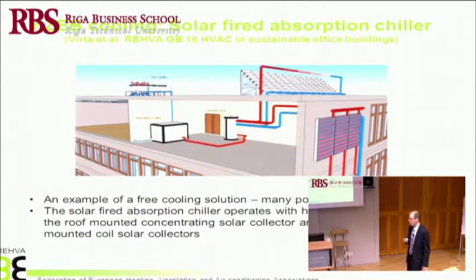In cold climate, maybe these cooling issues are not so severe. Actually, we can reduce cooling load very easily by having a relevant window size and solar shading options. And we can do this kind of buildings with common chillers. You can select, indeed, one with better seasonal energy efficiency ratio. There are many models available in the market, and the range of so-called ESEER values, European seasonal energy efficiency ratio values, is quite large. You can select from 2.5, let's say, to 5.5, depending on the chiller, and then you can use a very conventional system, but once again based on high efficiency components.